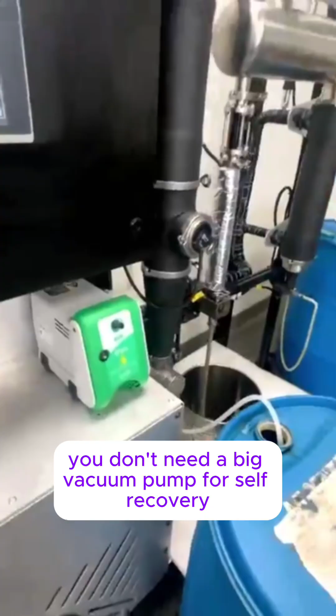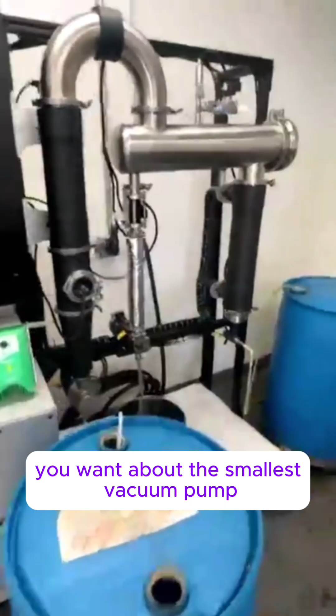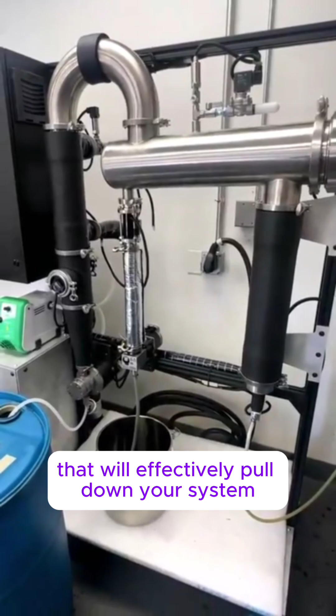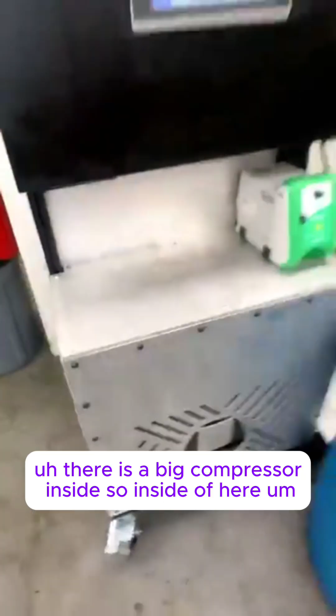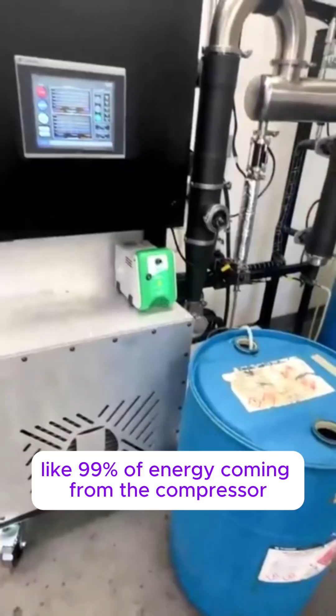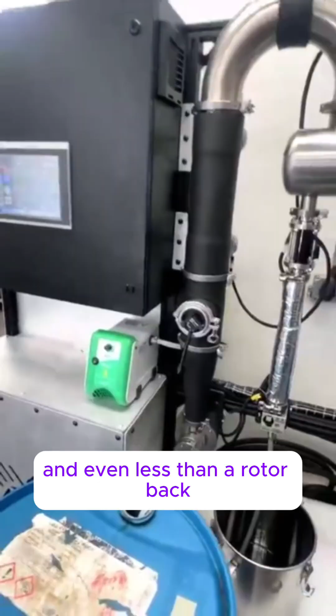You don't need a big vacuum pump for solvent recovery. In fact, for most solvent recovery systems, you want about the smallest vacuum pump that will effectively pull down your system. There is a big compressor inside. So inside of here is the heat pump system. So most of the energy from the process, like 99% of the energy, is coming from the compressor, which is simultaneously the chiller for the condenser and the heater for the evaporator. So that's the magic of the system, which uses only about a quarter of the electricity of a traditional falling film, and even less than a rotovap.